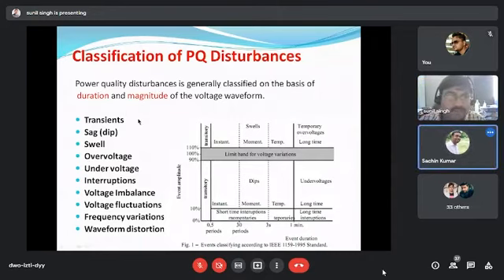Okay. So the power quality, this is the sag, swells, over voltage, under voltage, and now comes the interruption. If our voltage falls under this segment, here 0.5 cycle to 1 minute, and below 0.1 per unit, then it is known as the short term interruption. And if it is more than 1 minute, it is known as the long term interruption. And some special types of power quality disturbances are also there, which are not defined from this characteristic. They will be defined later on. Okay. So come to this.